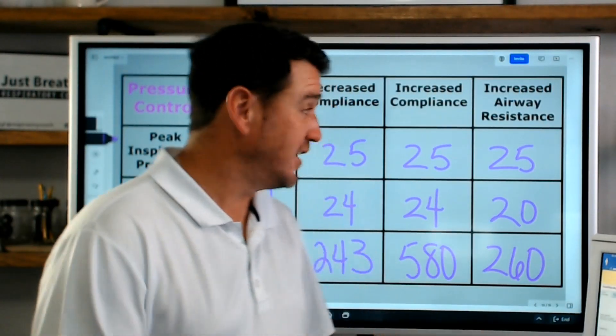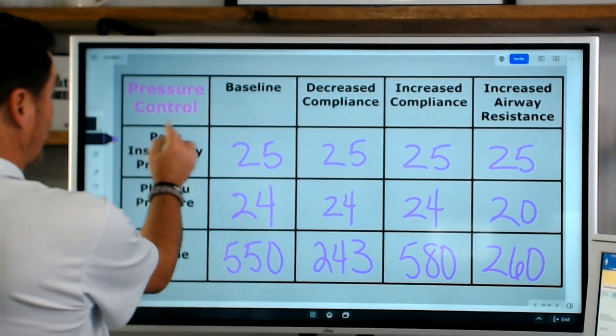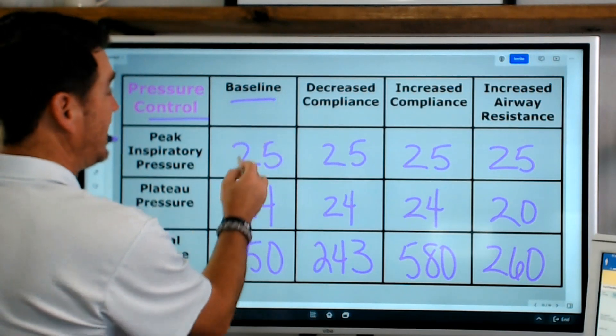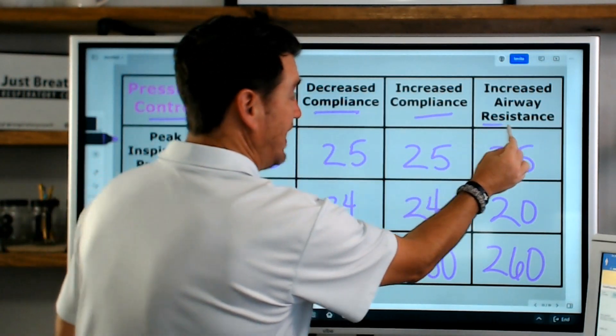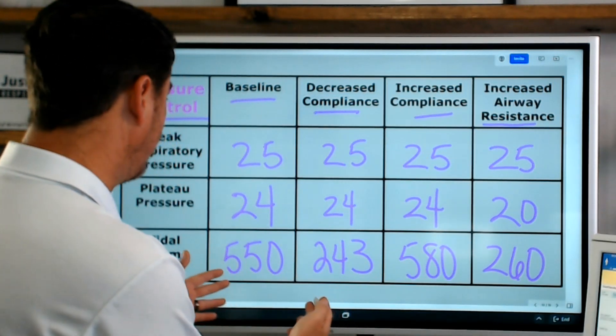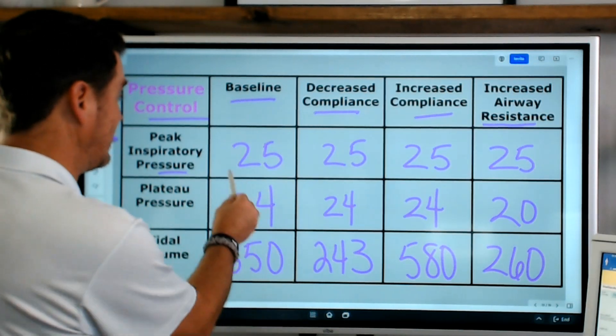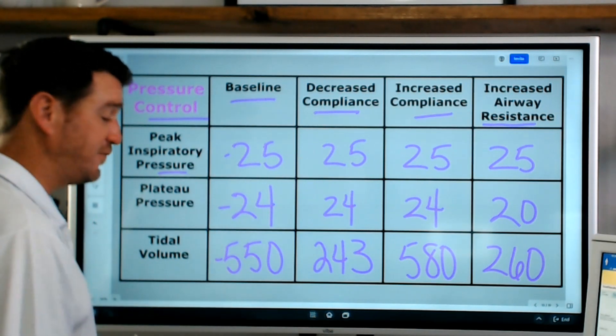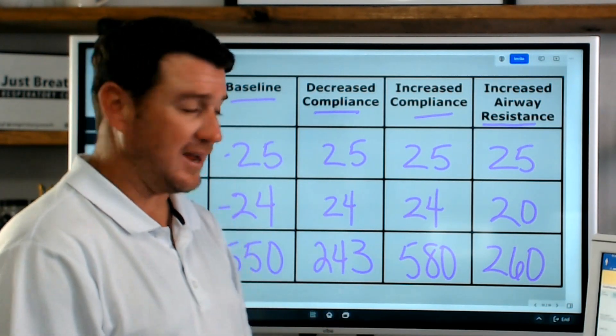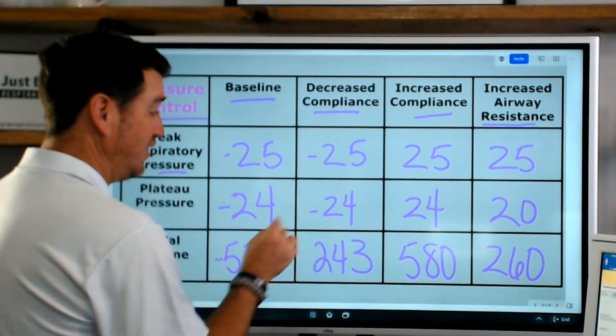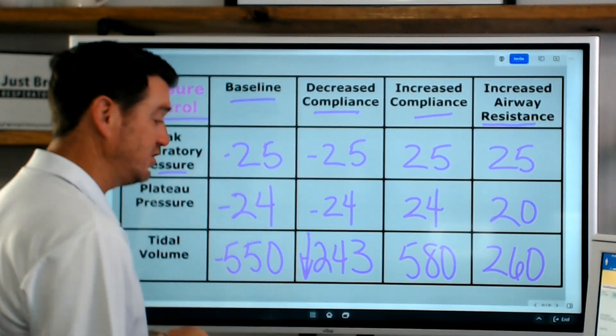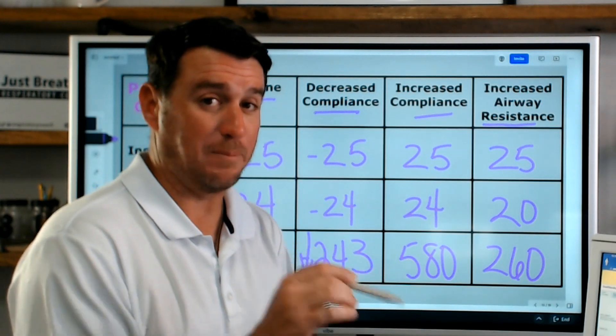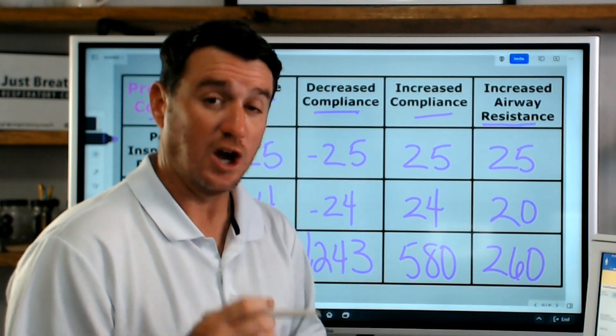So we've been looking at the ventilator and I've been writing numbers down - here's what those numbers look like. We're in pressure control. We started from a state of baseline, then decreased compliance, then increased compliance, and then increased airway resistance. Peak inspiratory pressure at baseline was 25, plateau pressure was 24, and tidal volume was 550. When we decreased compliance, inspiratory pressure stayed at 25, plateau stayed at 24, but tidal volume went down to 243. In pressure control, if compliance decreases, then tidal volume decreases - but pressure stays the same, because pressure is set.